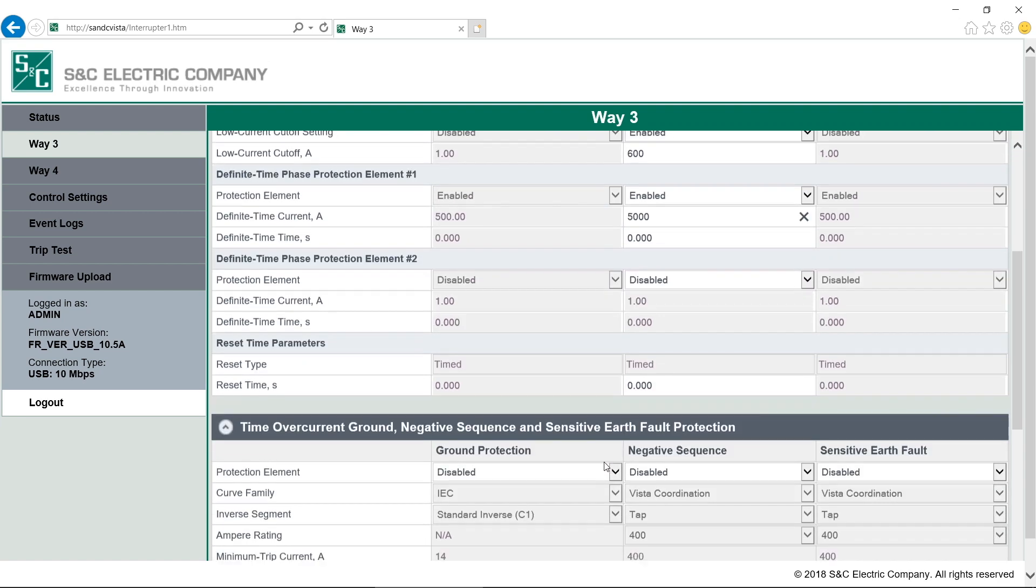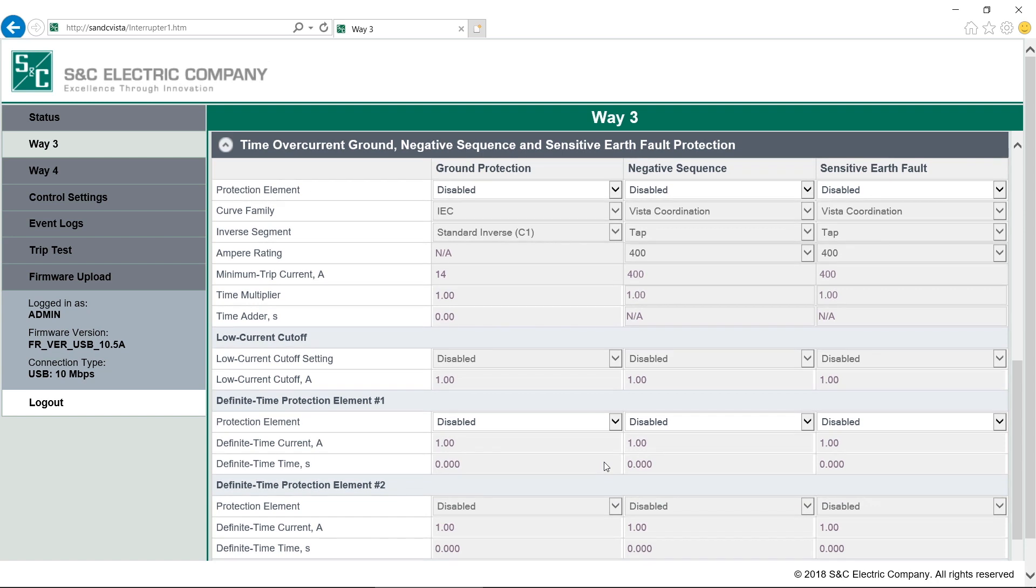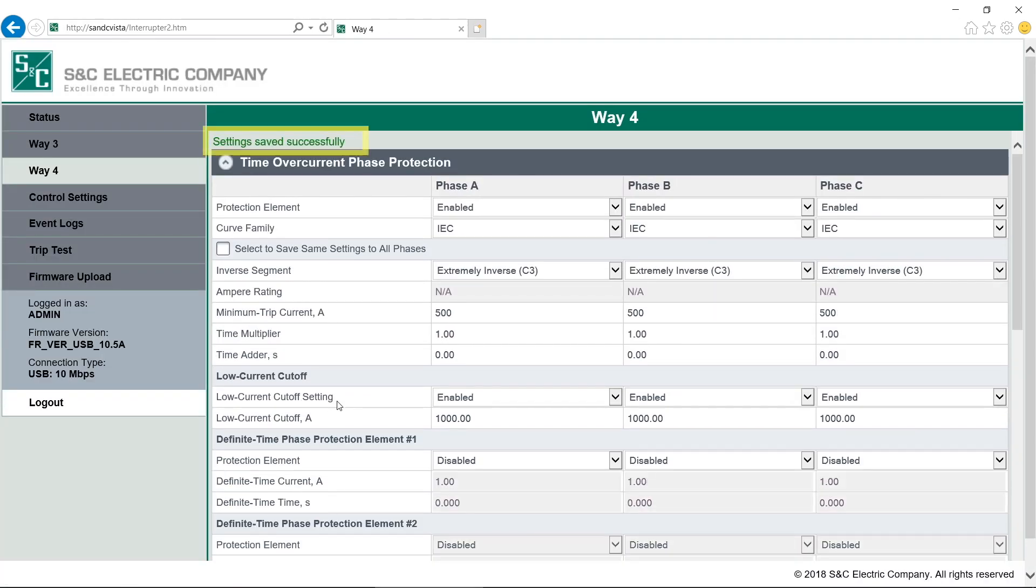The same is true below, where we find Ground Protection, Negative Sequence and Sensitive Earth Settings. Say we want to add Ground Protection. We first have to enable Ground Protection and all the values change from gray to white, which tells us they can be edited. To save our settings, just click Save at the bottom of the screen. We'll see this green text telling us that the save was successful. That's generally how protective settings are selected.